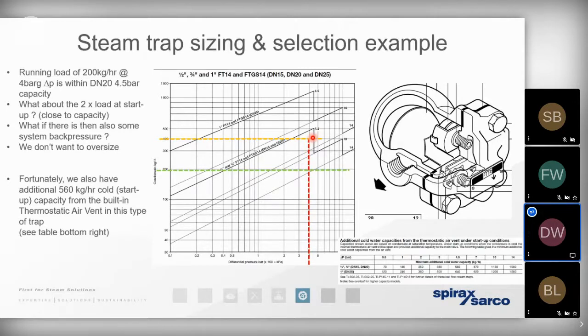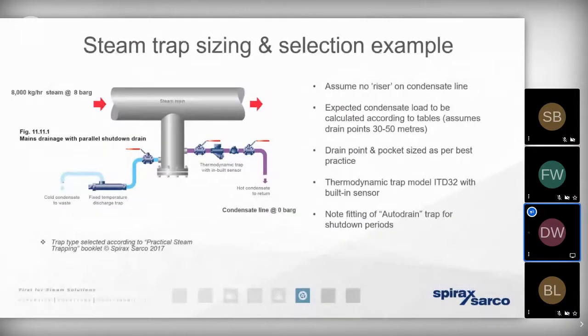for the process. But if we're looking at removing the condensate from the distribution pipework, then we've got a different set of criteria to consider. We mentioned that we could be distributing the steam at 8,000 kilograms per hour at a pressure of 8 bar gauge. And again, if we're discharging the trap to atmospheric, we would refer to that as having an 8 bar differential pressure. On this occasion, you can see we've got a secondary trap located here coming off the dirt pocket. It's what we refer to as a fixed temperature discharge trap or an auto drain.